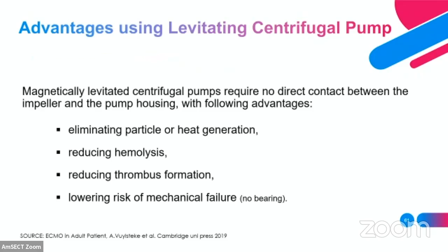One of the first concepts to introduce is the shearing force during the use of a volumetric centrifugal pump. This is a volumetric color Doppler, similar to a color Doppler evaluation of the velocity and the speed that is translated into stress and hemolysis. You can see from the center of the pump to the last point of the blade that the velocity, the speed of the blood, changes and indicates the vortex, the circus. That means that the shaping and the number of the blades inside the pump have important significance.